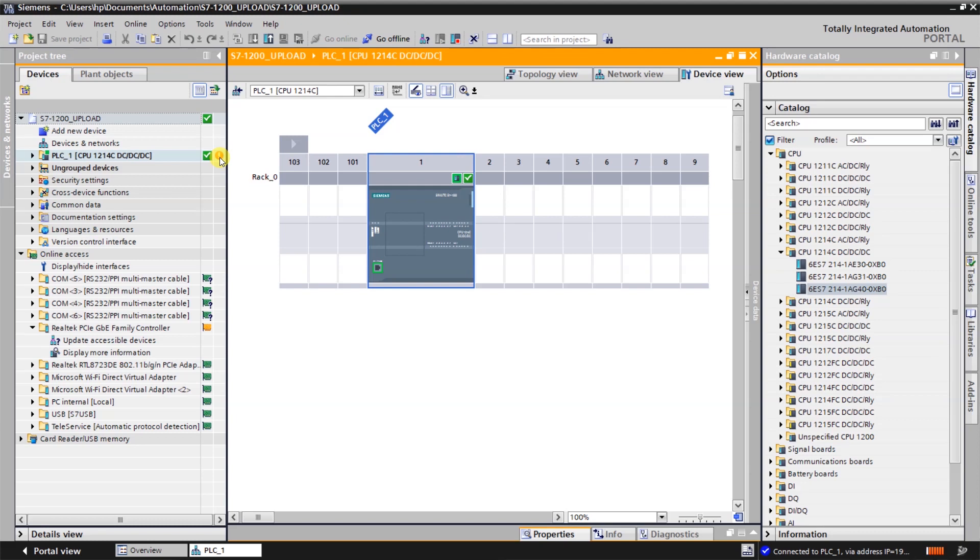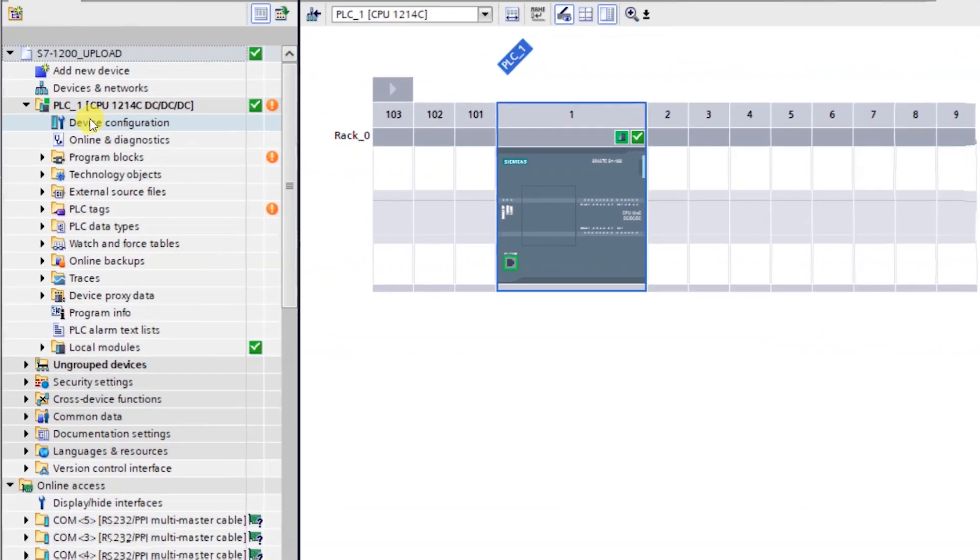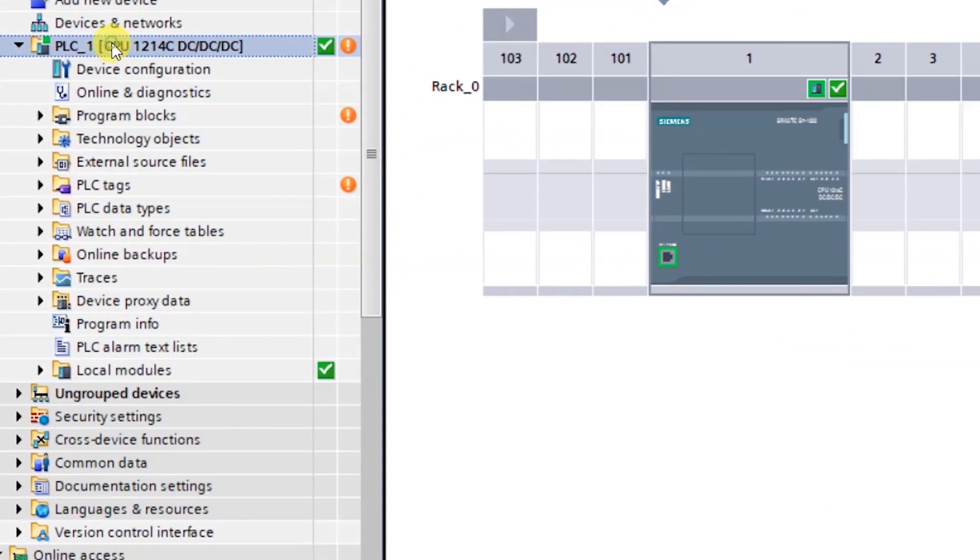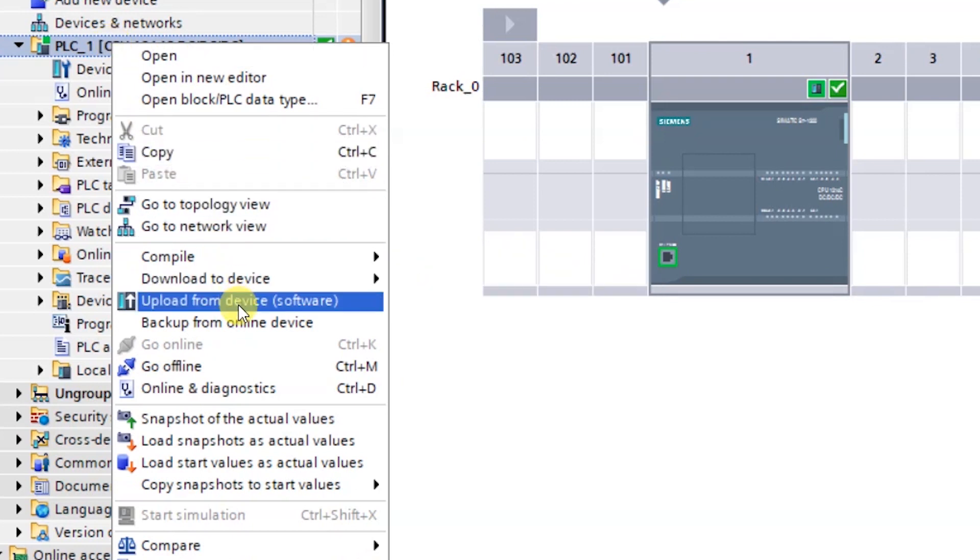Here an orange symbol has been shown in the software in the project tree. That means online and offline configuration of the software is different. Now you can take the upload from the PLC. Just select the PLC in the project tree, right-click on it, and click on upload software only.